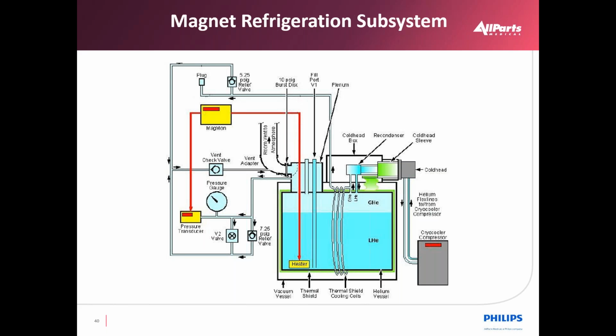The MR magnet has several components, the primary one being the magnet itself and the refrigeration section. The refrigeration systems used can be either 10 Kelvin models or 4 Kelvin models. The first is not able to recondense the helium gas into a liquid, therefore it has a higher helium boil-off or loss than the 4K magnets in which the gas can be converted back into a liquid. Magnets of this type are said to be zero boil-off systems.